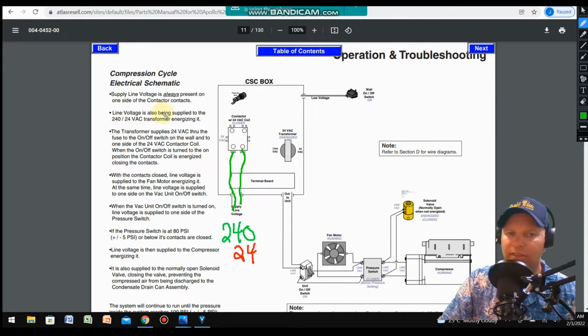Now, the line voltage is also being supplied to the 240 volt to 24 volt transformer, energizing it. So the transformer's here, and you have a parallel circuit. You have your 240 volts going to the contactor as well as to the transformer. I've gone ahead and illustrated the 240 volts in green. No particular reason why, just that it's a different color.